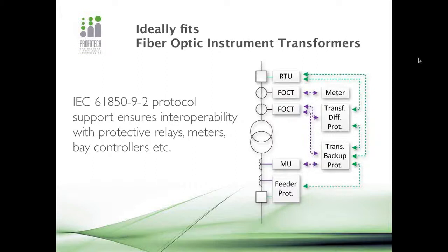This blue line stands for the IEC 61850-9-2 protocol, which makes it possible to transfer sampled values of current and voltages to secondary devices like meters and protection devices. And the green lines stand for GOOSE messages, which is another protocol used for transfer of binary signals between devices. So all these communications are possibly made through a single wire. It means that it's not actually a wire, it's the information wire. It could be just fiber optic or copper UTP cable.